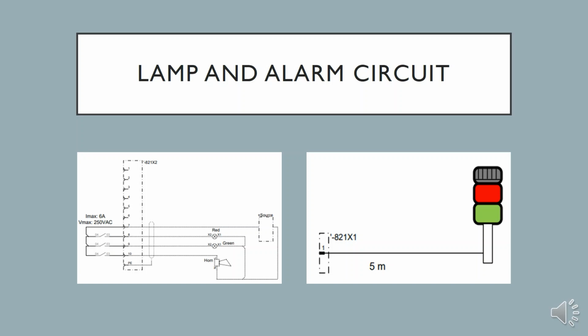For the lamp and alarm circuit, as we can see on the circuit, there are three switches, normally open: switch 1 connected to the red indicator, switch 2 connected to the green indicator, and switch 3 connected to the horn. These three switches are normally open and will be triggered if any switch is triggered and changes from normally open to normally closed.